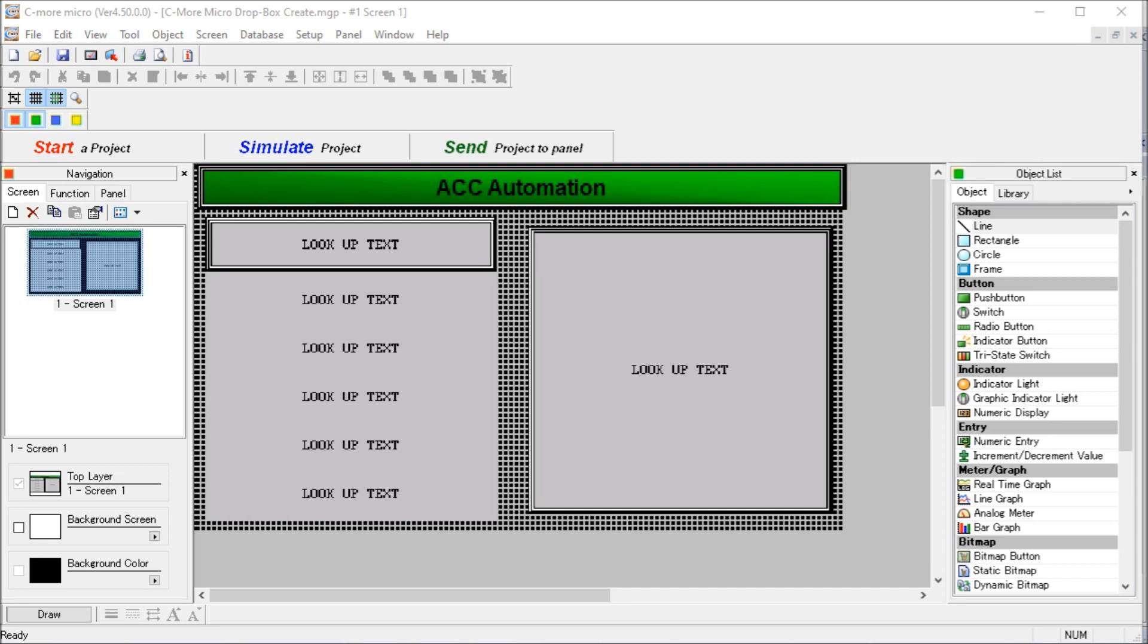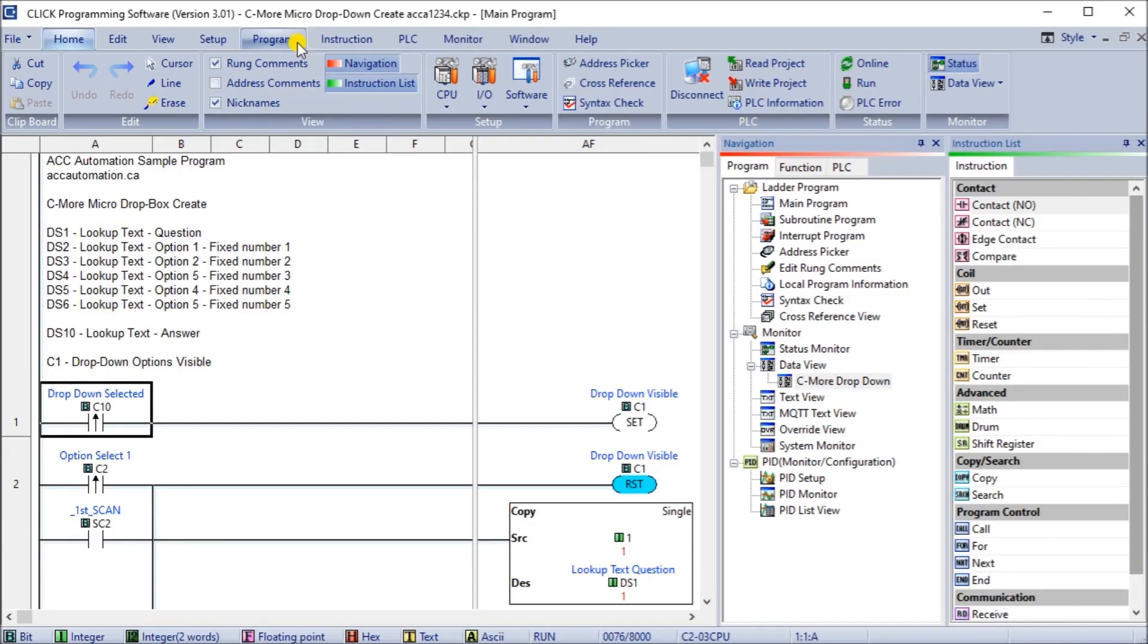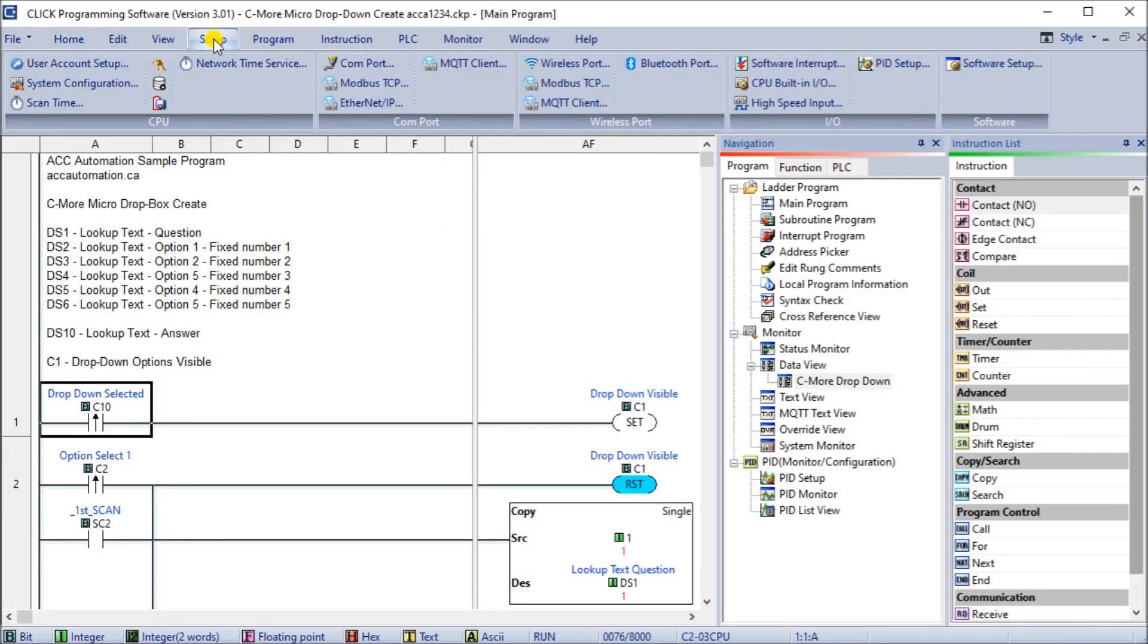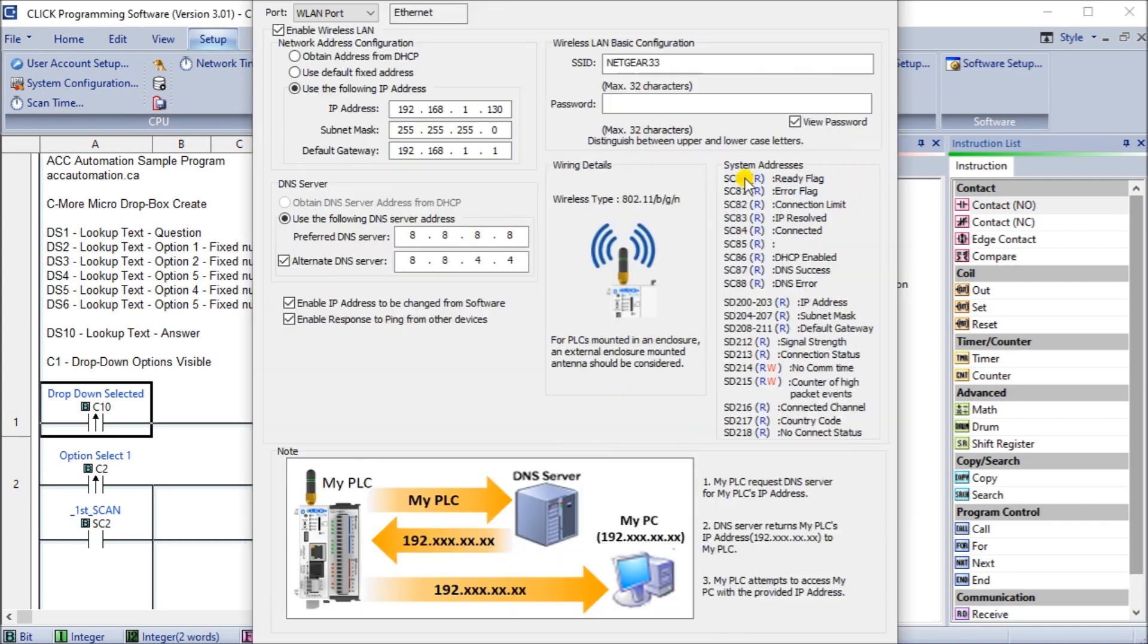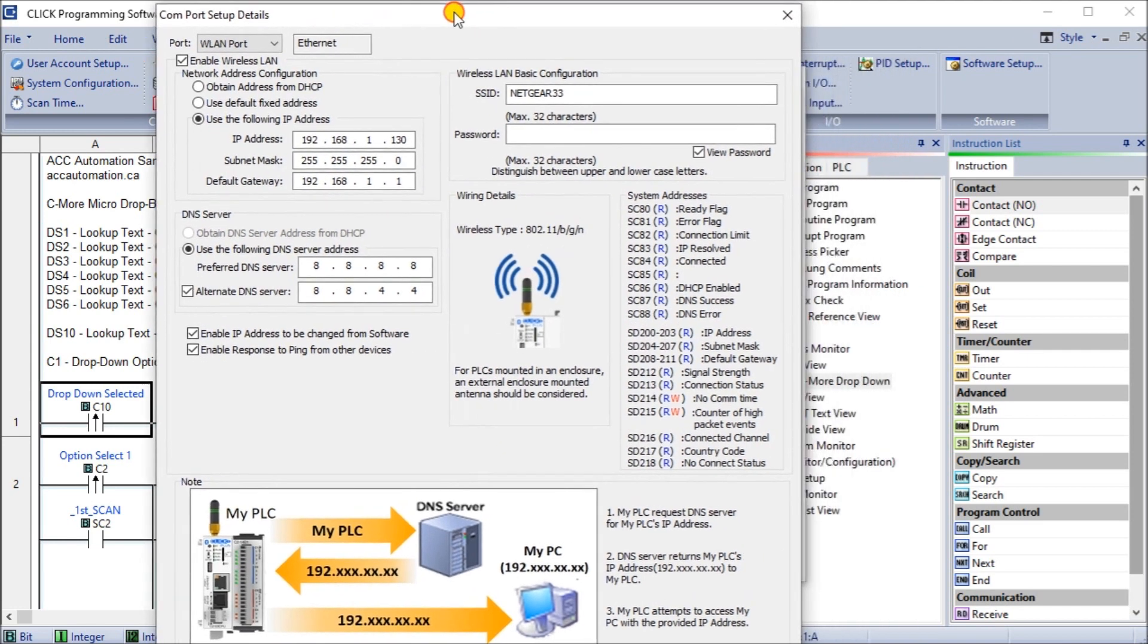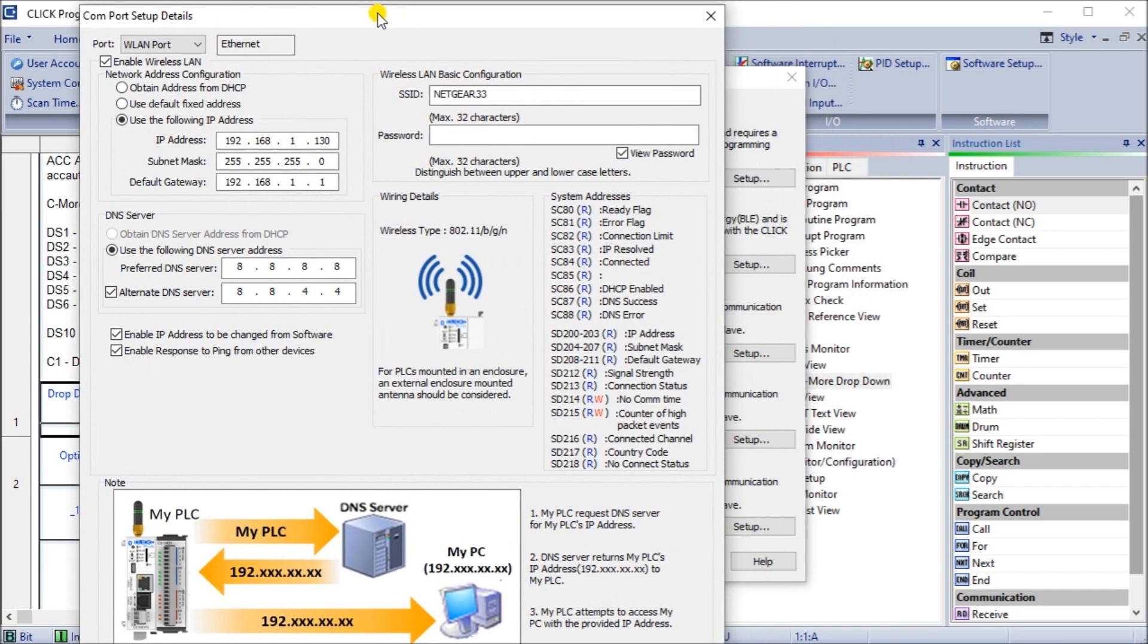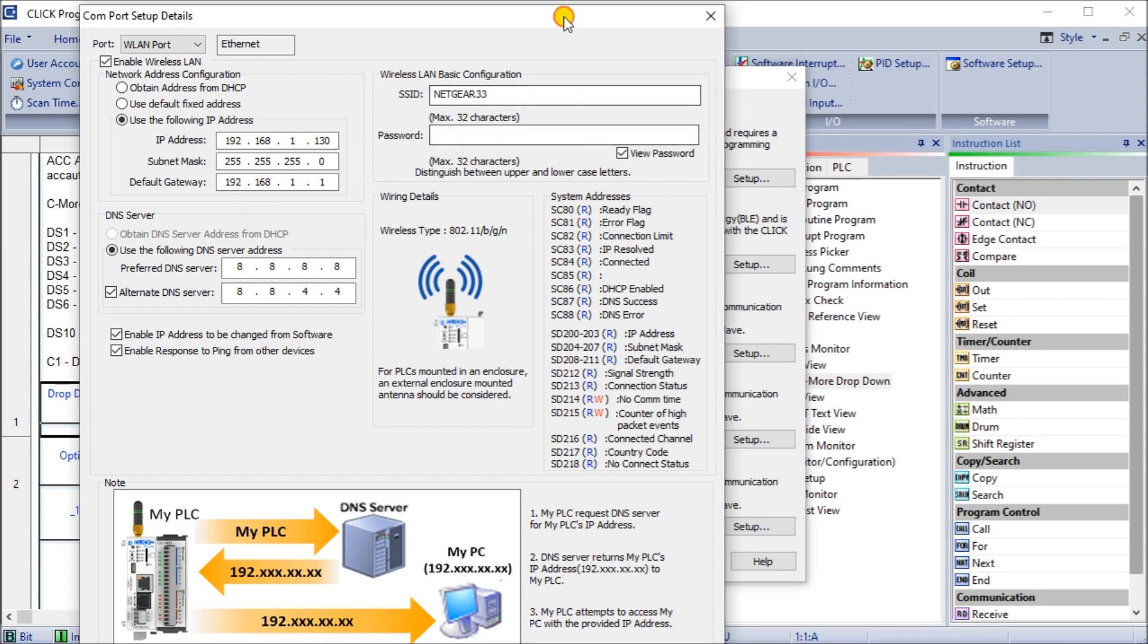So the first thing we'll do is take a look at our Click PLC software and we will look at our setup and our COM port and we'll see that our WLAN and our setup on our Wi-Fi here is set for an IP address of 192.168.1.130. So that tells us where we're going to be connecting to on our Click from our C-more micro.